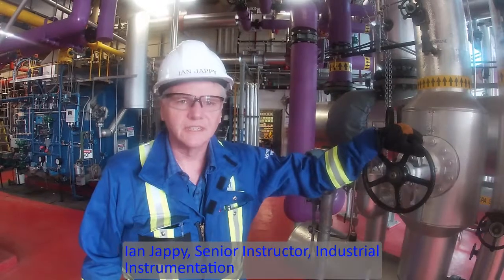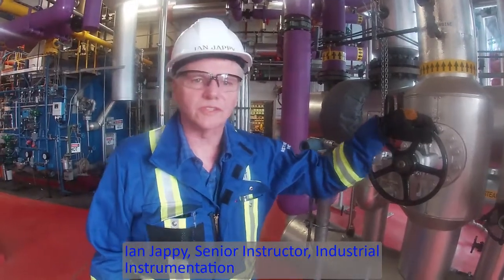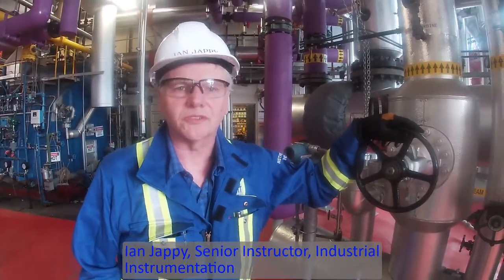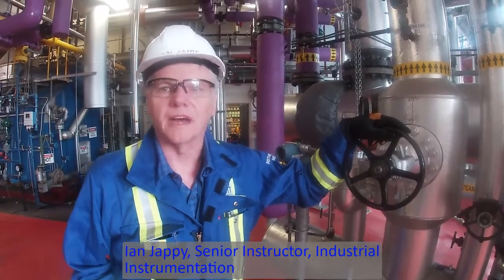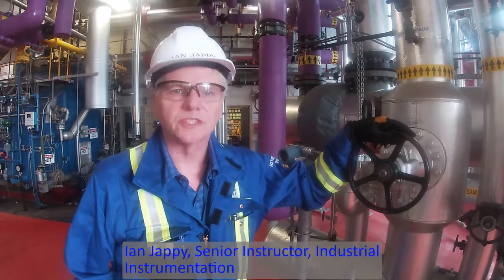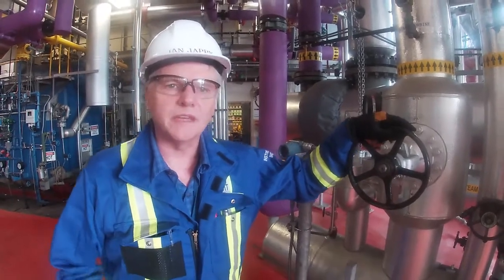Okay, hi guys. So today we are going to start up the Shinko steam turbine. At this point right now, we already have the boiler online. We brought that up earlier this morning. And now we need to start to warm up the lines that are going to go to the Shinko.